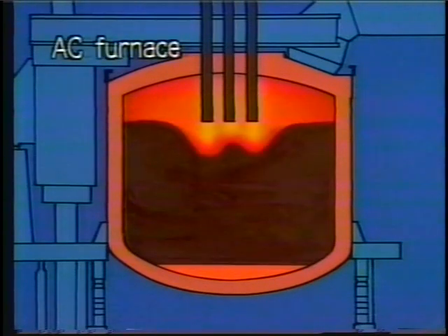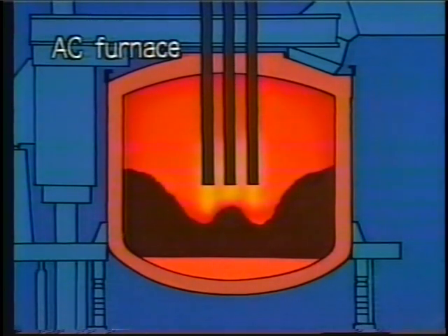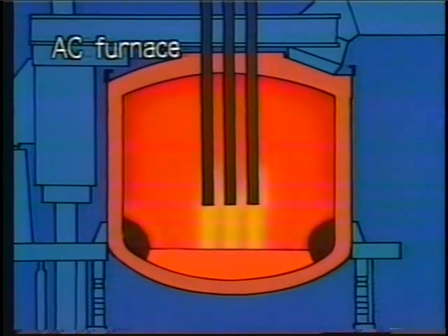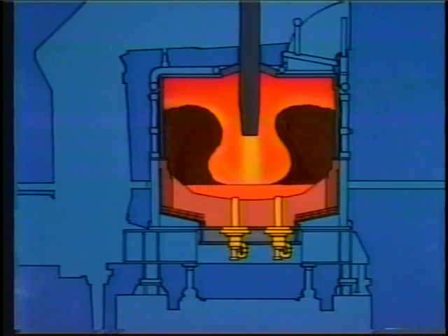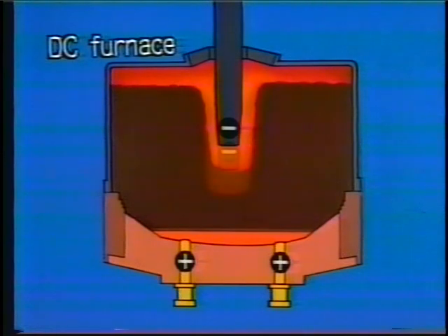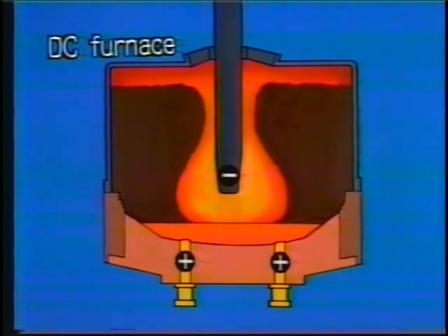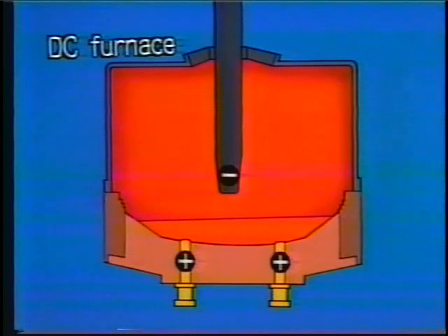With an AC furnace, three electrodes are used to generate electric arcs of 6,000 degrees Celsius. The arcs gradually burrow their way into the charge, and the electrodes have to be raised and lowered repeatedly to prevent short-circuiting. But with a DC furnace, overcurrents present no problem. All the power is concentrated in a single electrode, and the boring process is almost instantaneous, since the electrode generates an extremely hot arc of 8,000 degrees Celsius. When the furnace bottom electrode is positively charged, the heat around the molten charge can be increased even further, and there is virtually no need to raise and lower the electrode because the charge melts in a concave shape.